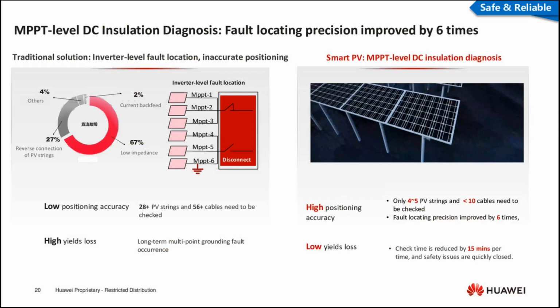And most of the DC faults, as I mentioned before, are common in utility scale plants. There are other pain points also faced by the majority of our customers and the majority of people in the PV industry at utility scale. That is the precise identification of fault location. Most inverters will do the RISO detection before feeding into the grid, which is actually called insulation monitoring. We have now brought a high amount of granularity into this diagnostics, which is done at the MPPT level with high accuracy. This smart feature is very important to detect and position DC side faults accurately, which is very helpful for utility scale power plant projects.